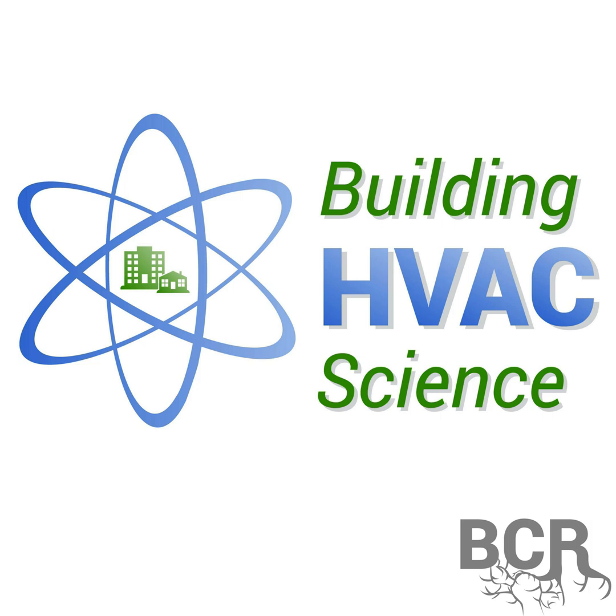Sure. During times of no occupancy, you won't have any CO2 generated, right? And things like wind, even in a highly sealed home, like a passive house level home with very low infiltration, a wind speed change from 5 miles per hour up to 20 miles per hour is more than 4 times an increase in ventilation. It's a factor of 16, since infiltration goes with the square of the wind speed.